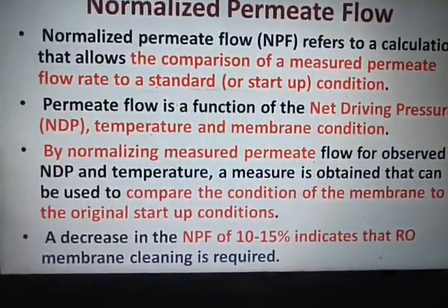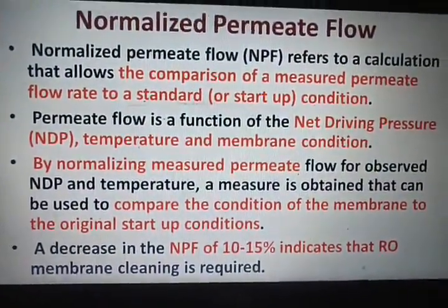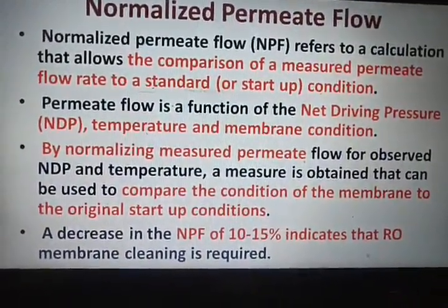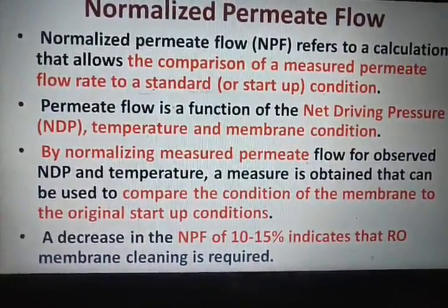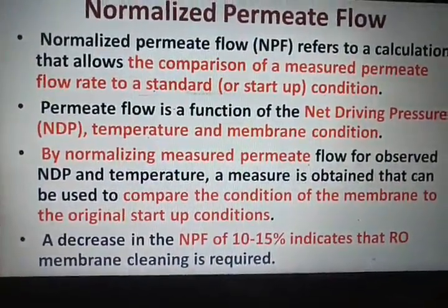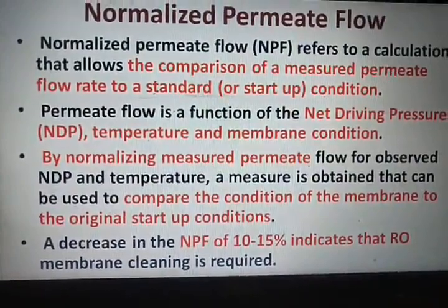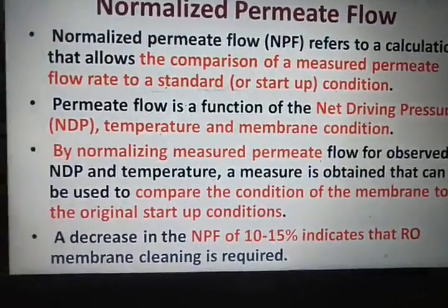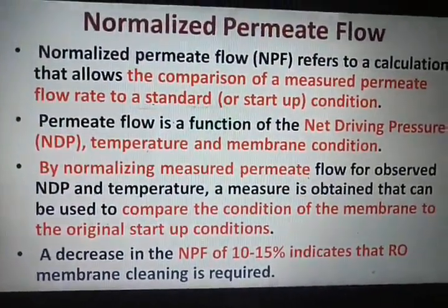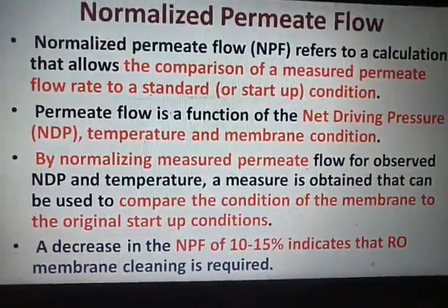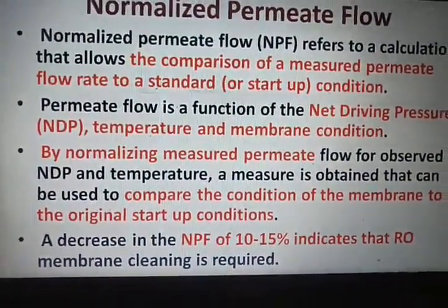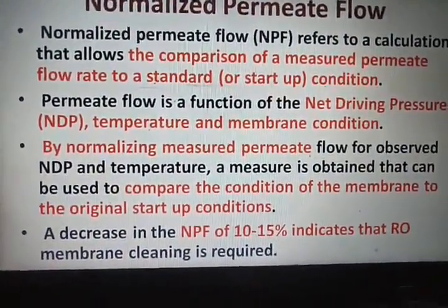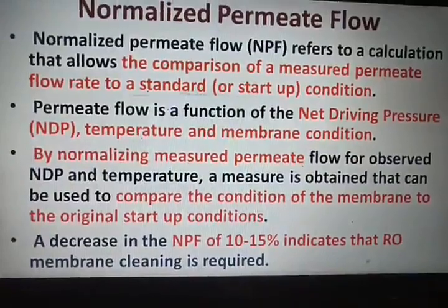That means as the membrane process continues, parameters like the net driving pressure and temperature change and the membrane starts to foul. Depending upon that, the permeate obtained or the water treated will be affected, thereby affecting the membrane process in total. This normalized permeate flow is taken as a reference for membrane cleaning or replacement of the membrane.